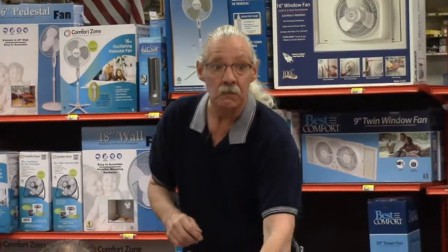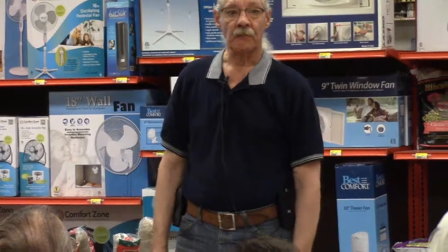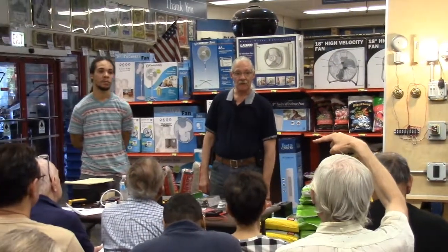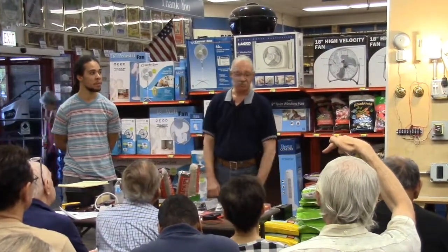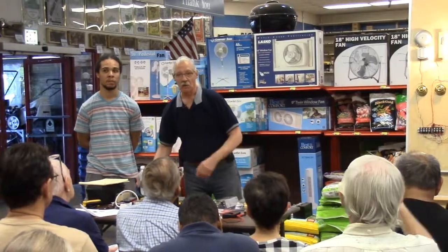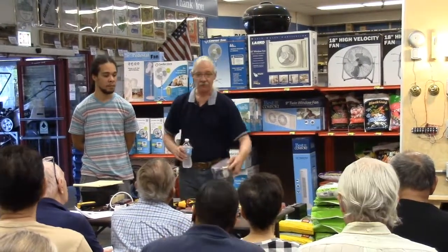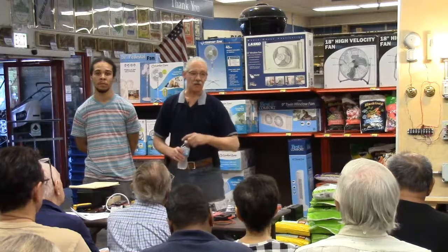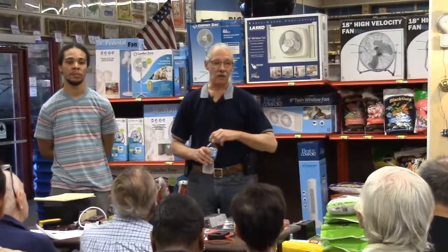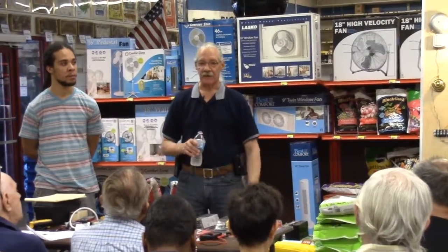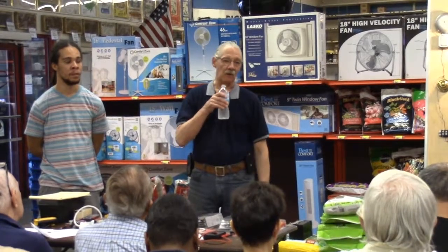So if the meter says 70 volts and I put a light bulb across the two wires, it's not going to go on? No. Or even be dim? No, it won't light the light bulb. It won't activate the solenoid in the solenoid tester. A phantom induced voltage will not light a light bulb.